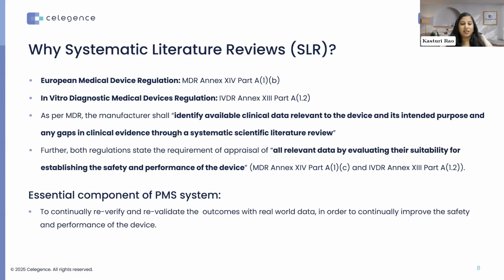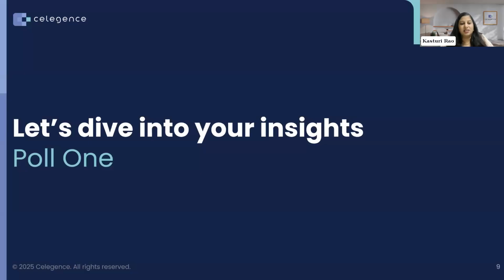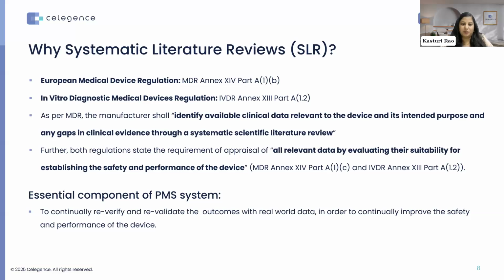Also, SLRs are needed to show compliance to EU MDR and IVDR. For example, the MDR clearly states that the manufacturer shall identify available clinical data relevant to the device and its intended purpose, and also identify any gaps in the clinical evidence through a systematic literature review. It also states the requirement to appraise all relevant data by evaluating their suitability for establishing the safety and performance of the device.